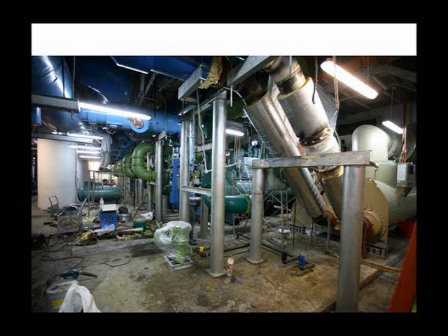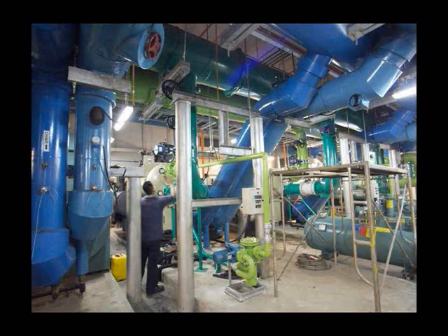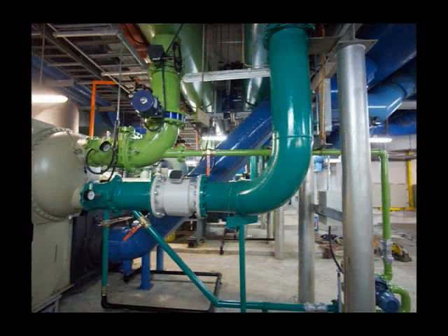And this is all the old stuff you can see. Tremendous U-turns. So straighten out. In real-world retrofits, we don't have the time, the space, the ability to shut down to do what we like. There's a 28-inch header overhead. We cannot move it. It would cost hundreds of thousands to move it so that we could get good flow conditions. So this flow meter is not in a good place, but hey, that's all we can do.